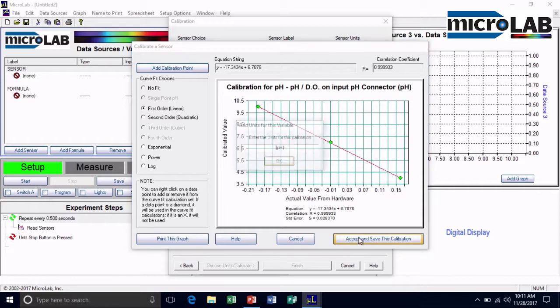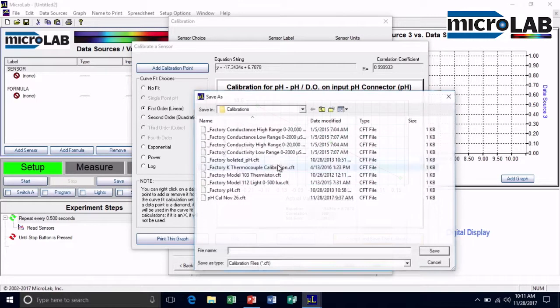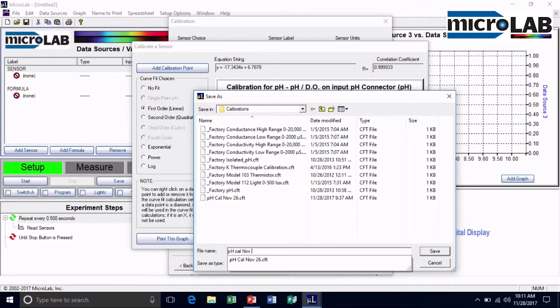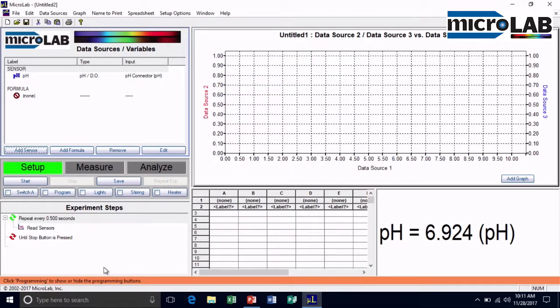Now, since we have a good calibration, I can accept and save it. Units are going to be pH. I'm going to call it pH Cal November 27th. And I'll save that. I'll say finish. The water solution is about pH 6.9. So what we've done is take an uncalibrated pH electrode, use 3 known pH samples to calibrate it, and we got a good calibration. And that's basically all there is to it.